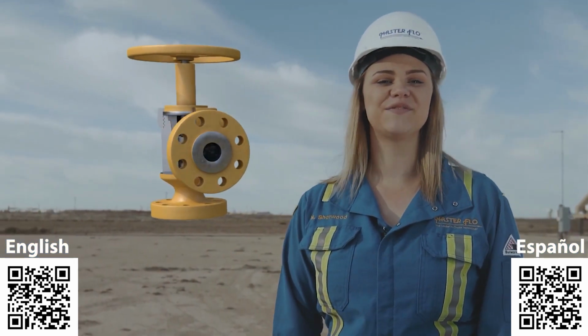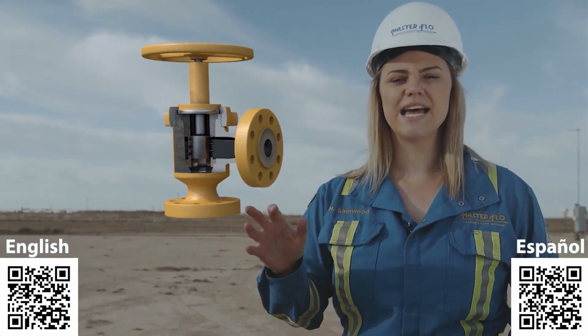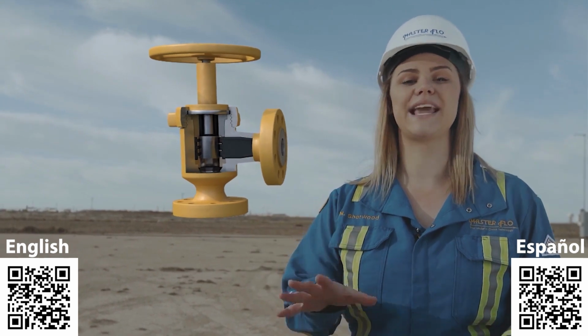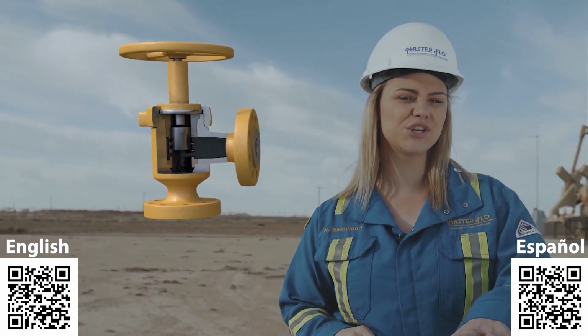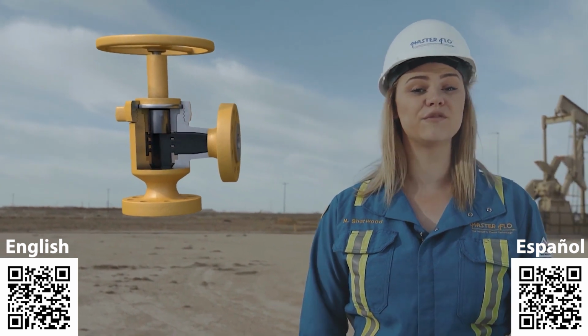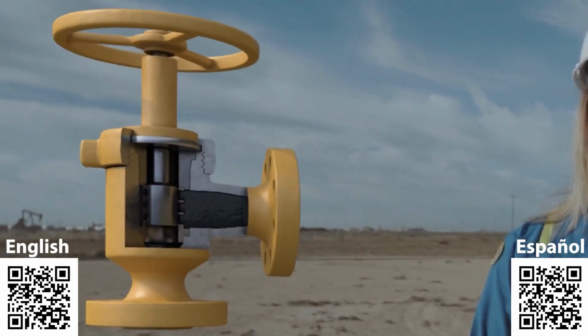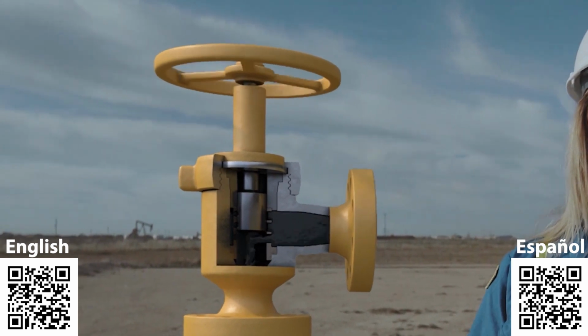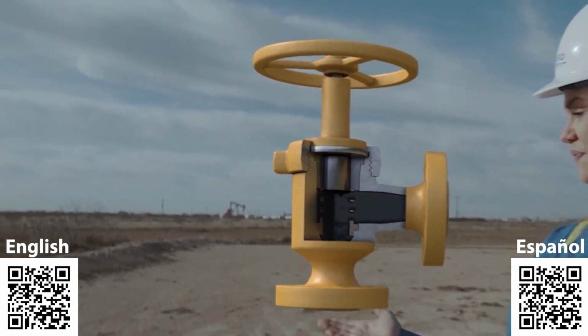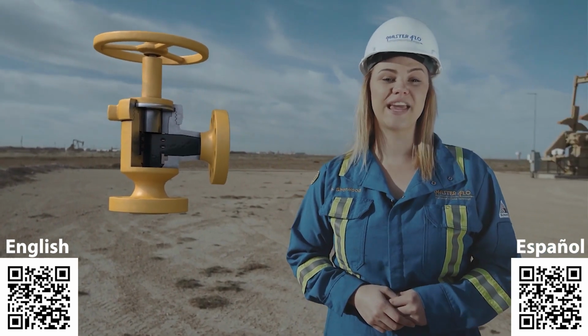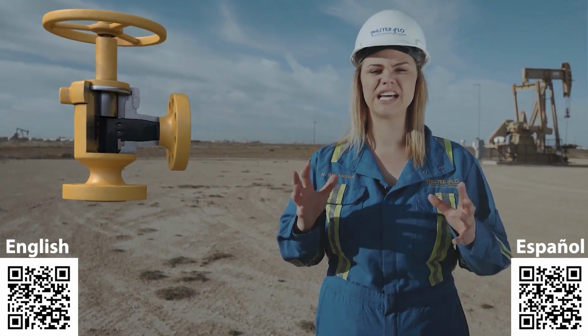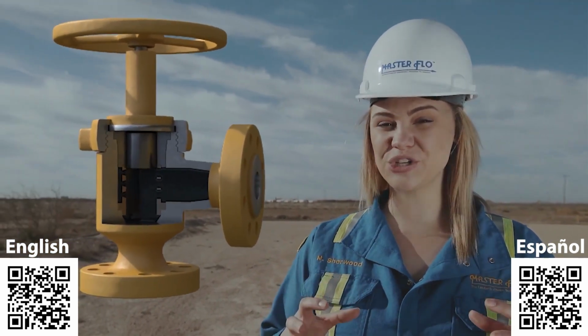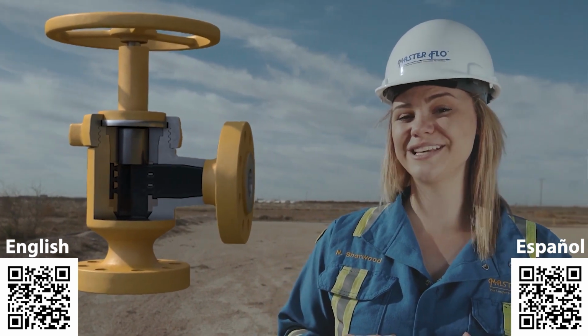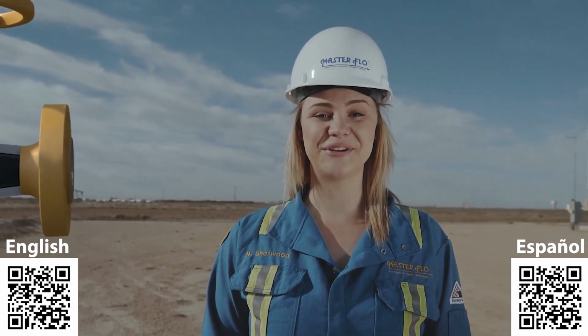Our next choke valve has a fixed cage and internal plug. A stem connected to the plug allows the plug to be moved up and down by the rotation of the wheel, changing the size of the opening for the flow. Inside the choke, fluid circulates in the annulus between the body and the cage. The location of the cage openings forces the streams to collide in the middle. Impinging streams cause hydrostatic back pressure and allow using fluid energy against itself, resulting in minimal wear of valve material.